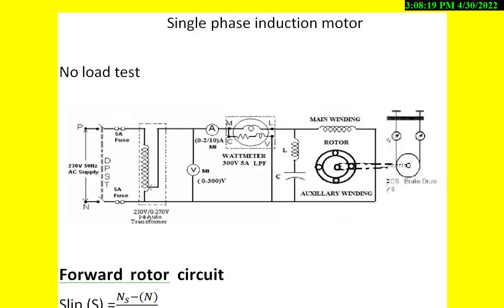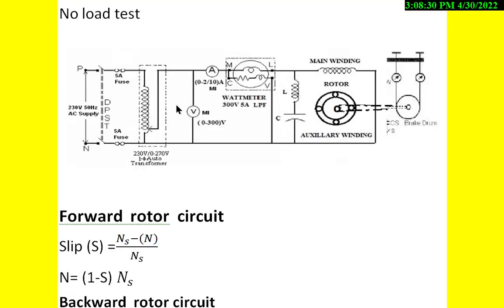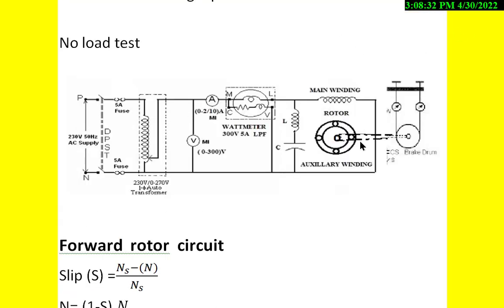Friends, today I will discuss the single phase induction motor no load test and the blocked rotor test. The connections for the single phase induction motor no load test and the blocked rotor test are like this. This is the single phase auto transformer. This is the single phase AC supply with switch connection.